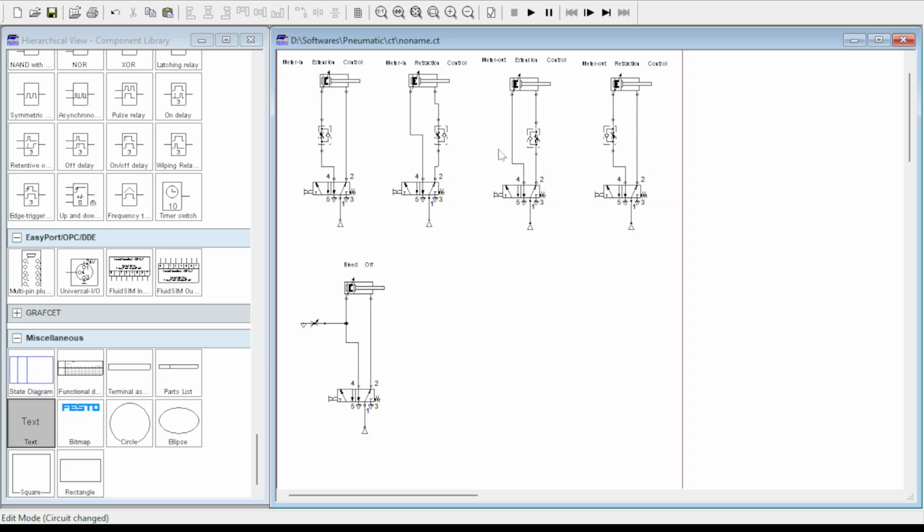Whereas in bleed off, it decreases the speed of actuation of the cylinder. Whereas when you close the throttle completely in meter in and meter out circuits, you try to completely block the flow into or out of the cylinder. Whereas if you block the throttle in a bleed off circuit, you basically stop the leakage that is happening. You're stopping the bleeding off of the compressed air. Thereby, the entire compressed air goes into the cylinder, such that the speed will be increased.